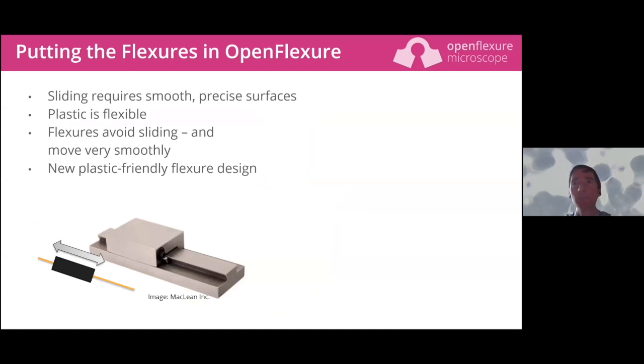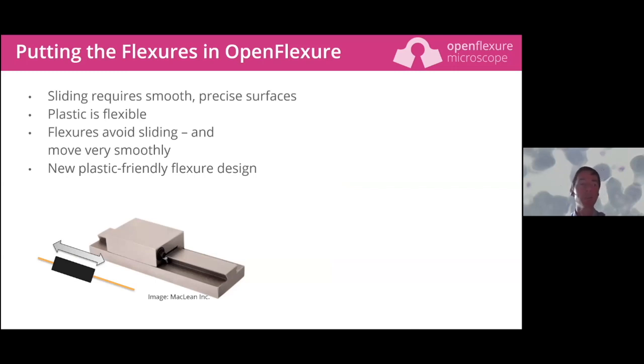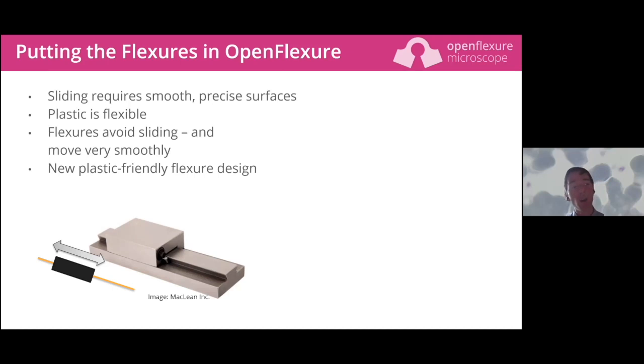So why is that difficult to engineer? When you make a translation stage, you want to move something in a straight line - nice and smoothly, without wobbling left and right or up and down. Generally you make two metal parts: a track and a slider. The slider has to fit very tightly over the track so it doesn't wobble sideways, but not so tightly that it binds - which means very precise tolerances, very smooth surfaces, and very hard surfaces so it doesn't wear down.